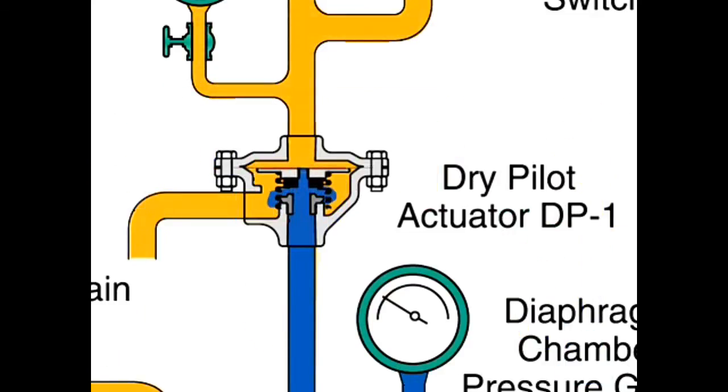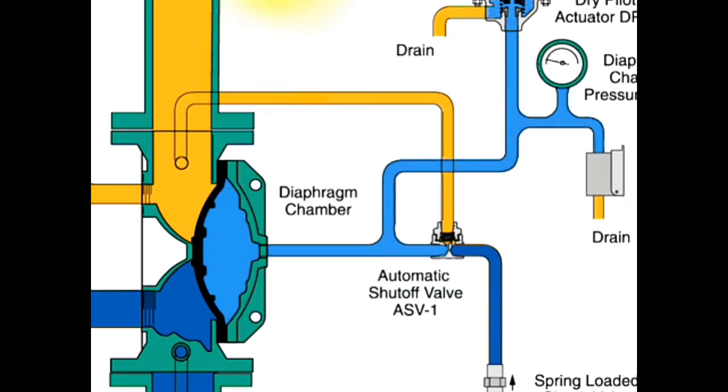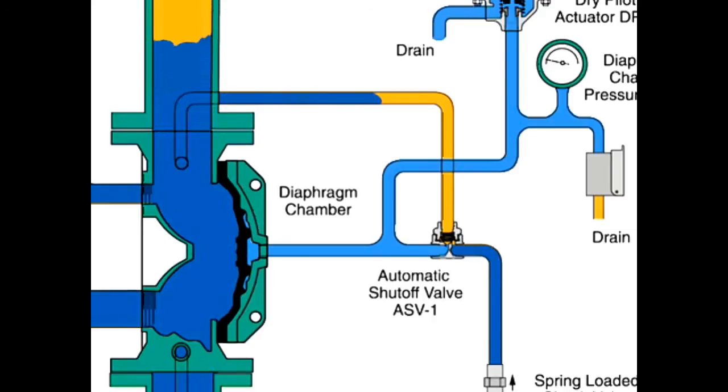When a fire sets off a dry pilot sprinkler, air pressure is released from the pneumatic pressure pilot line. In turn, the dry pilot actuator opens and releases water from the diaphragm chamber faster than it can be replenished through the one-eighth inch restriction in the automatic shutoff valve. The rapid pressure drop in the diaphragm chamber allows the diaphragm to open.